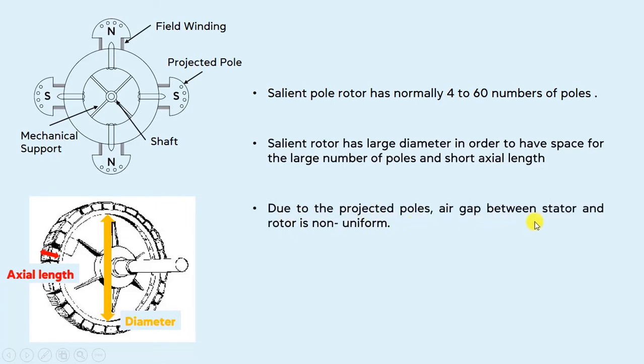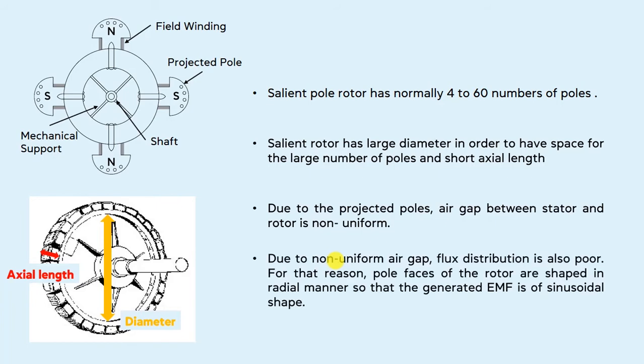Due to the projected poles, the air gap between the stator and rotor is non-uniform in the salient type rotor, which results in poor flux distribution. For that reason, the pole faces of the rotor are shaped in a tapered manner so that the generated EMF is of a sinusoidal shape. So due to the poor flux distribution, the pole faces are shaped in a tapered manner in order to achieve a sinusoidal EMF output in the case of salient type rotor.